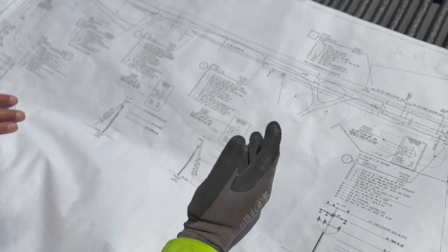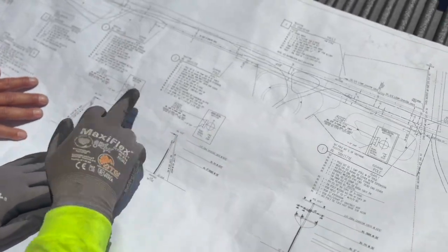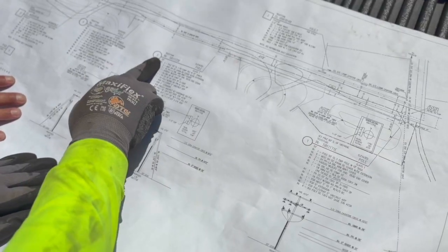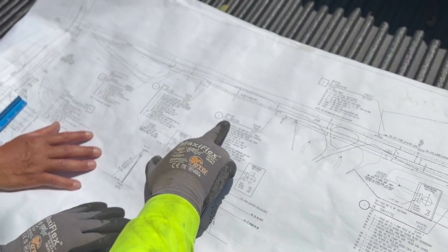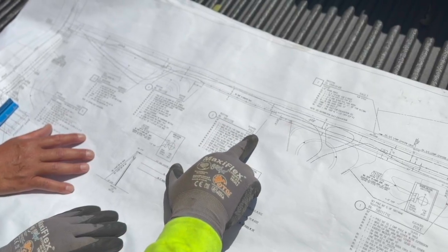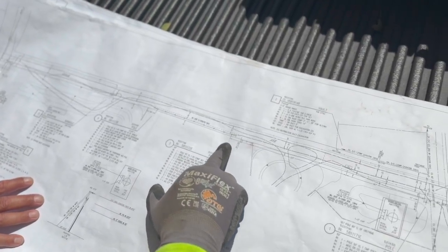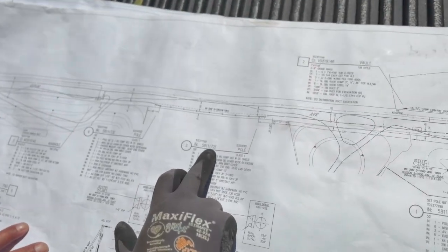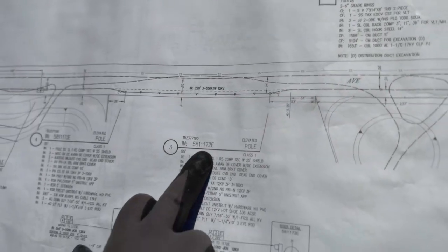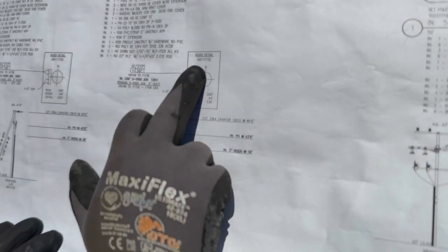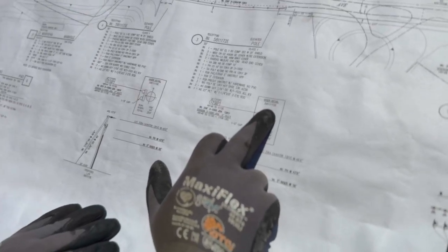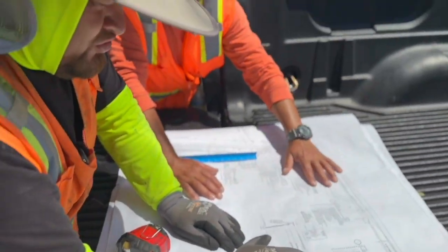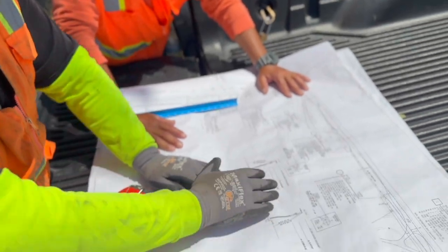And then when I go up to the next pole, that looks the same. Same thing, I'm going to go back to a different call out, and trace the solid black line all the way up to the pole. Then I'll read the numbers, and I'll make sure these numbers match with the riser detail that they're giving me here. So you do the same thing on all three of them.